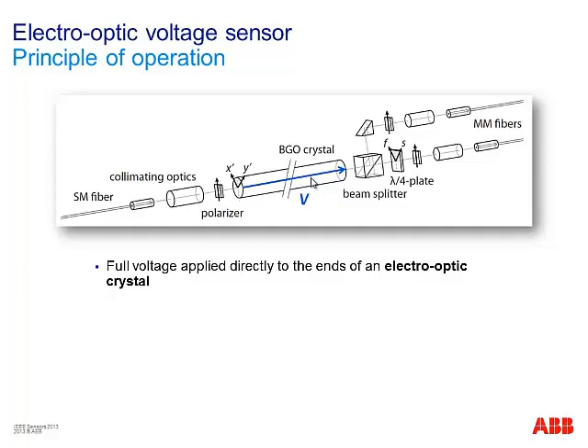You have a birefringence effect inside this crystal, which basically causes a differential phase shift between two light waves that propagate with orthogonal polarization. We achieve this by using this polarizer here, which is placed at 45 degrees with respect to the main axis of the crystal.